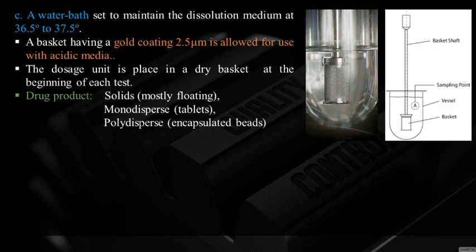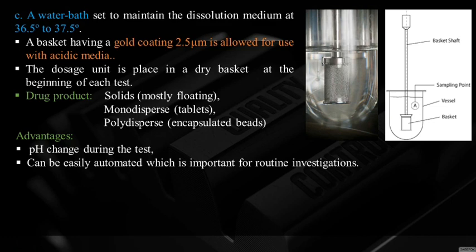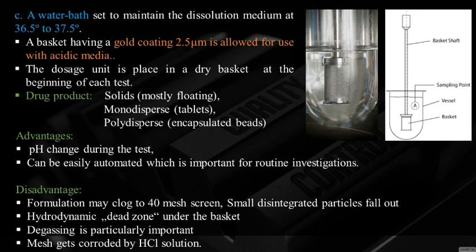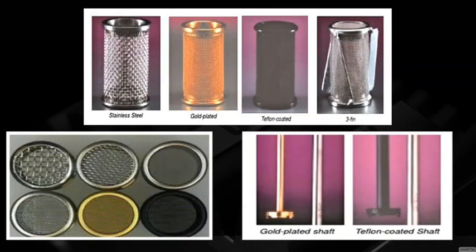Basket apparatus is suitable for solid, mostly floating, monodispersed tablets and polydispersed encapsulated beads. Advantages: pH changes during test can be done and the apparatus can be easily automated. Disadvantages: formulation may clog the 40-mesh screen, small disintegrated particles may fall out, a hydrodynamic dead zone may form under the basket, degassing is particularly important, and the mesh can corrode in hydrochloric acid. Different basket types include stainless steel, gold-plated, Teflon-coated, three-fin, with matching coated shafts.